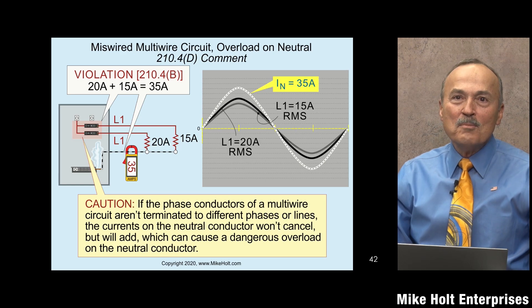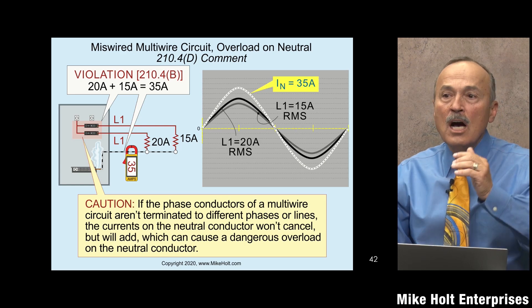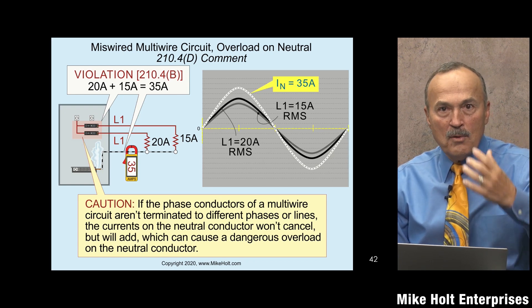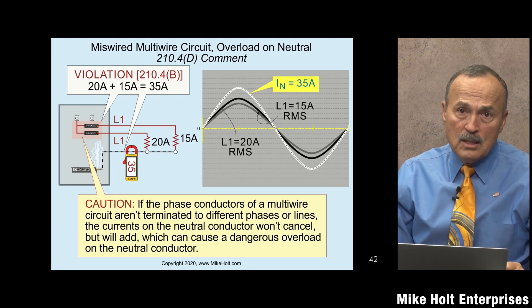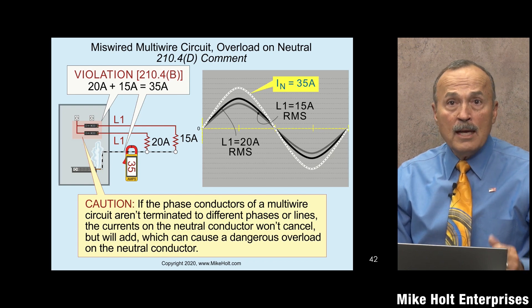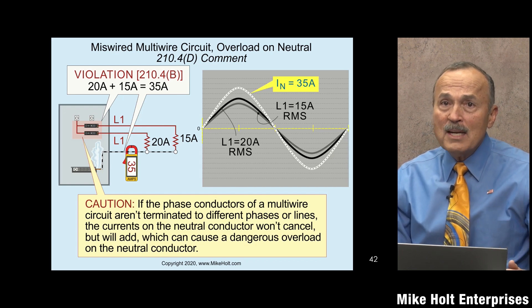The problem with multi-wire branch circuits is when someone who doesn't understand the hazards works on them — that's why we have the grouping requirements and the simultaneous disconnecting means. From a contractor's perspective, if you want separate conductors for every circuit with bigger conduit and more copper, that's great, but on a budget job multi-wire branch circuits are going to happen.